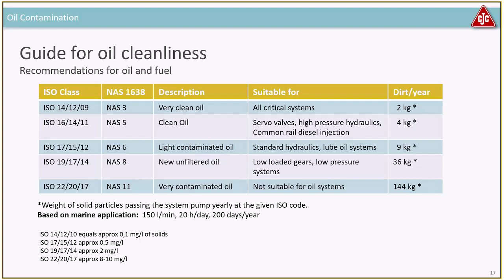I've seen systems in mining and cement working at ISO class NAS 11, getting only three to six months of pump life — maybe 4,000 hours maximum. I've also seen pumps working in clean oil that are 50,000 or 60,000 hours old and still functioning fine. So there's a big difference in how long a pump can last.